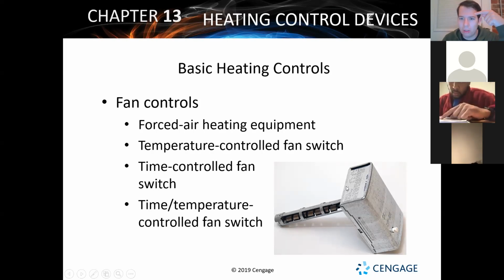This is sitting behind a wall. This is sitting in front of a wall, all right? Behind that wall is where your heat exchanger is. As the heat exchanger heats up the air around it, this bimetal coil is going to turn. It's going to turn a temperature dial inside of this switch. As it turns that temperature dial, it'll have its first setting, which will be to turn the fan on when the heat exchanger gets up to temperature. And so it'll turn the fan on once it gets up to temperature. And then once the thermostat says, yep, we're good, it'll turn the furnace off. And then the fan will stay on until it goes all the way back. That bimetal starts turning because it's cooling off, until it cools off all the way down to turn the fan off, which is the second temperature setting. So you got turn the fan on because the heat exchanger is warm enough, turn the fan off, the heat exchanger is cooled down enough.